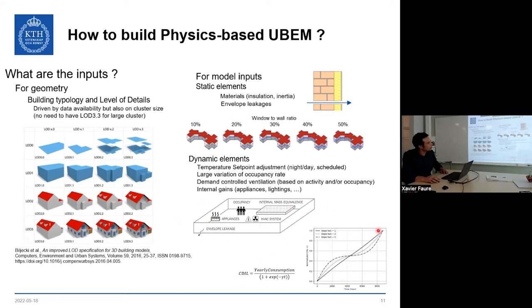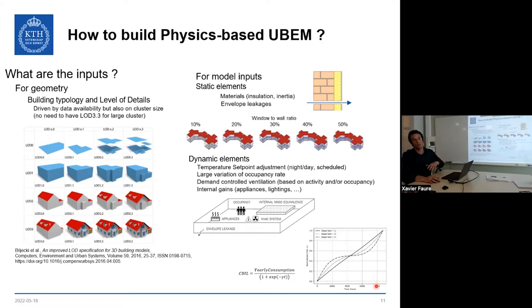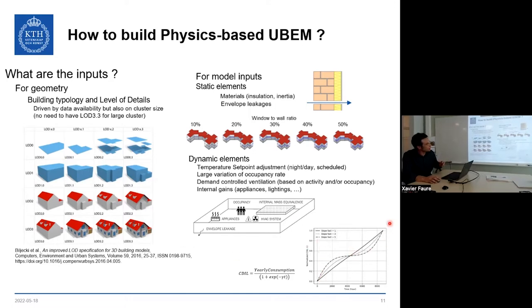For residential occupancy, we modeled occupancy, appliances, and lighting using a sigmoid curve representing released internal heat. A straight line would mean constant wattage year-round. Increasing the slope of the sigmoid allows you to model more heat release in winter — the gamma parameter controls this in the platform.